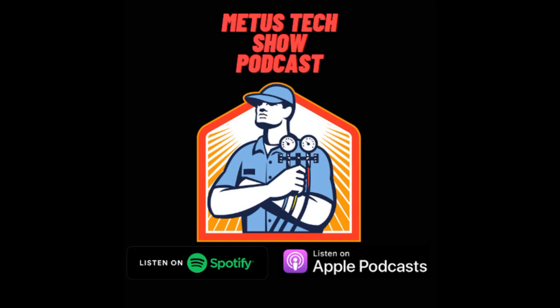What I like about it is it doesn't let you make a mistake. It's going to red flag you. So if you try and connect pieces of equipment that don't match, or you exceed a line set, maybe your branch run is limited to, let's say, 82 feet, and you have 82 feet and six elbows, and we know elbows add length to the pipe, it's going to red flag you and say, hey, you've just gone over, and you got to rework your installation a little bit. Diamond System Builder gets overlooked on the residential side quite a bit, but not anymore.